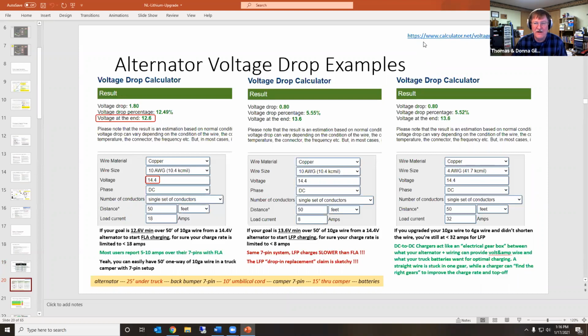This was an example of a voltage drop calculator I ran. This is a real nice one. Be advised, when you use this voltage drop calculator, it uses one-way wiring distance, assuming you're running negative and positive wires together at the same length. So when you say 25 feet in this calculator, it's really 50 feet of wire, 25 positive and 25 negative. So as you look at different calculators, you have to make sure which ones are one-way versus two-way when you type in the distance.